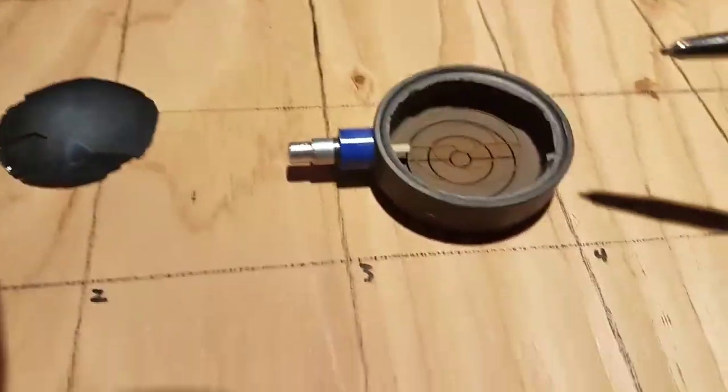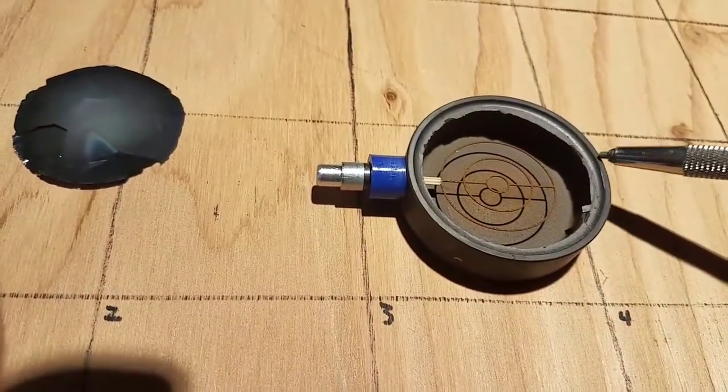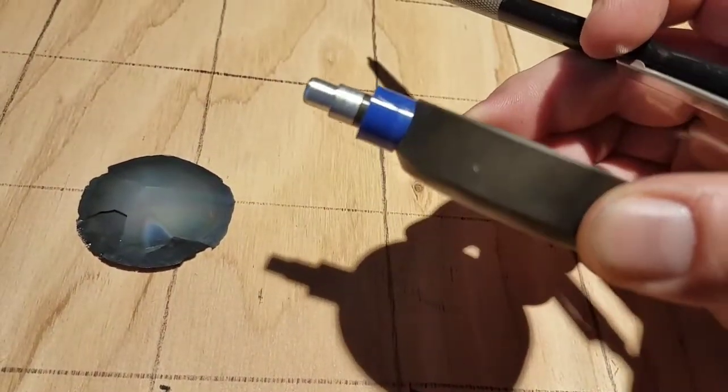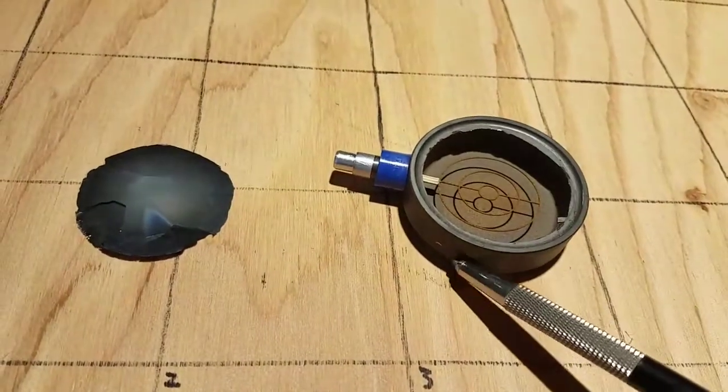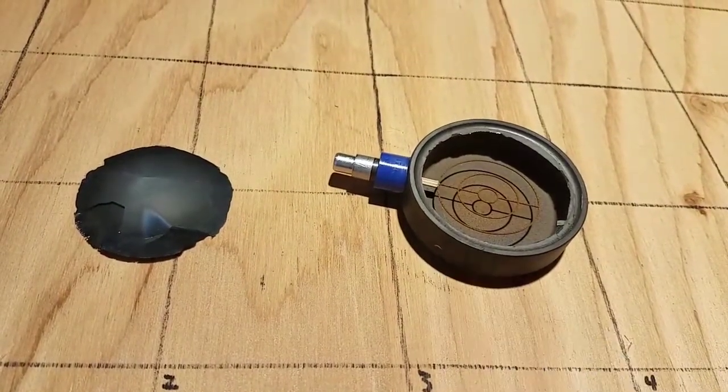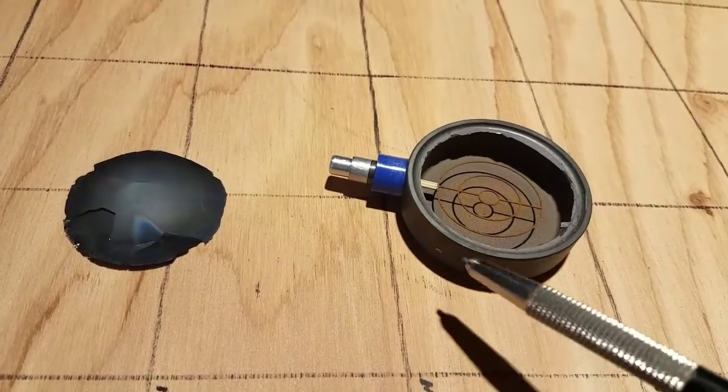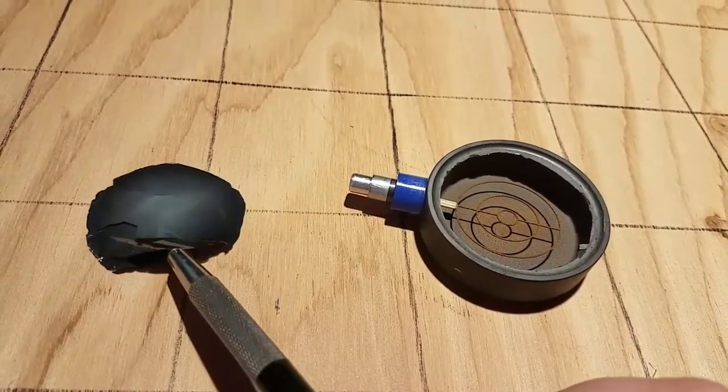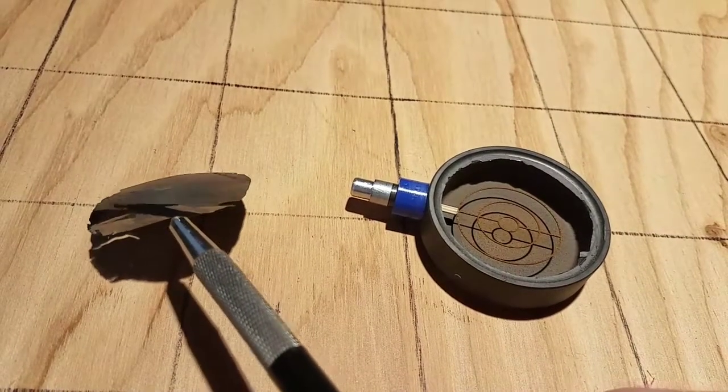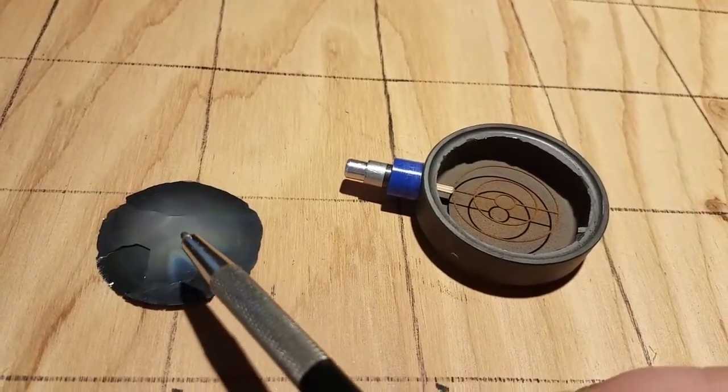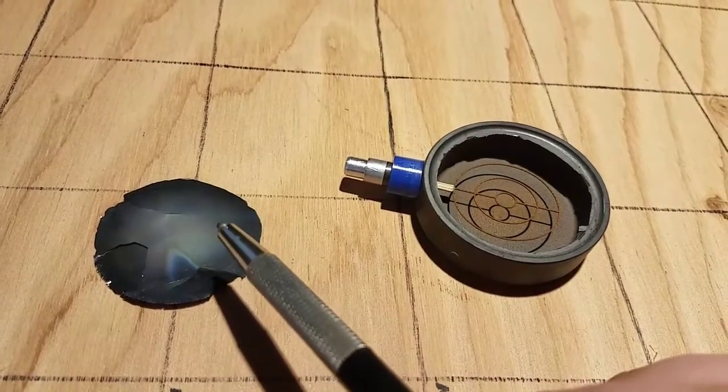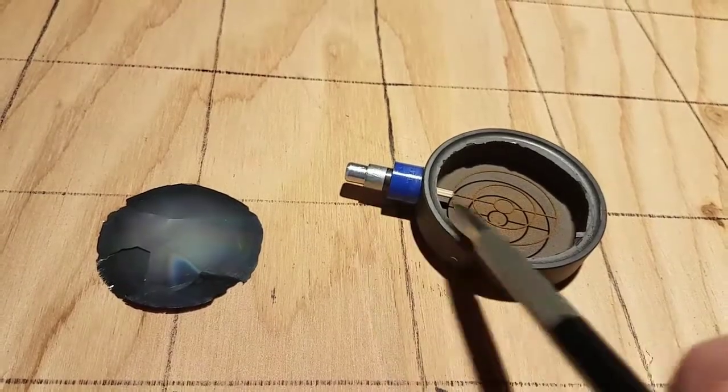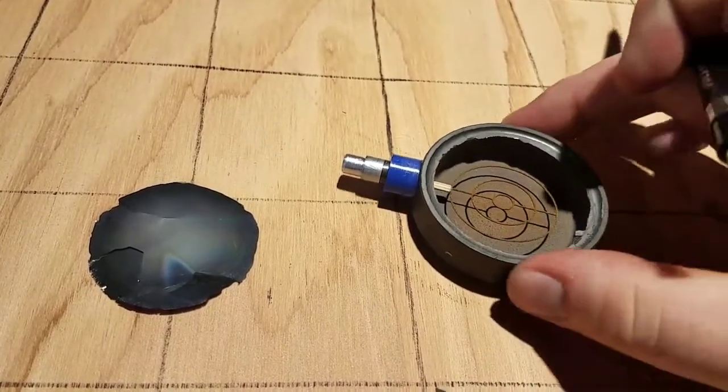So I'll actually show the real parts of the tube now. Here you can see the disassembled tube. This is the outer casing, the cathode, and you can actually see where the set screw here on the side connected that into the body of the probe. Here's the thin mica window, it's extremely fragile and very light. This allows alpha, beta, and gamma particles through while holding the halogen quench gas inside the body.